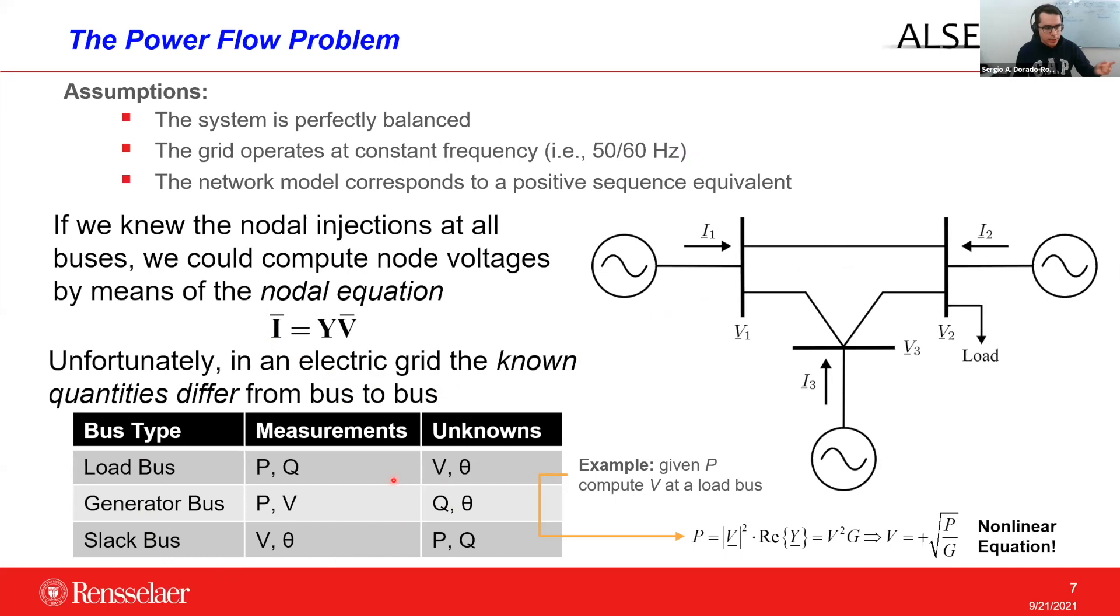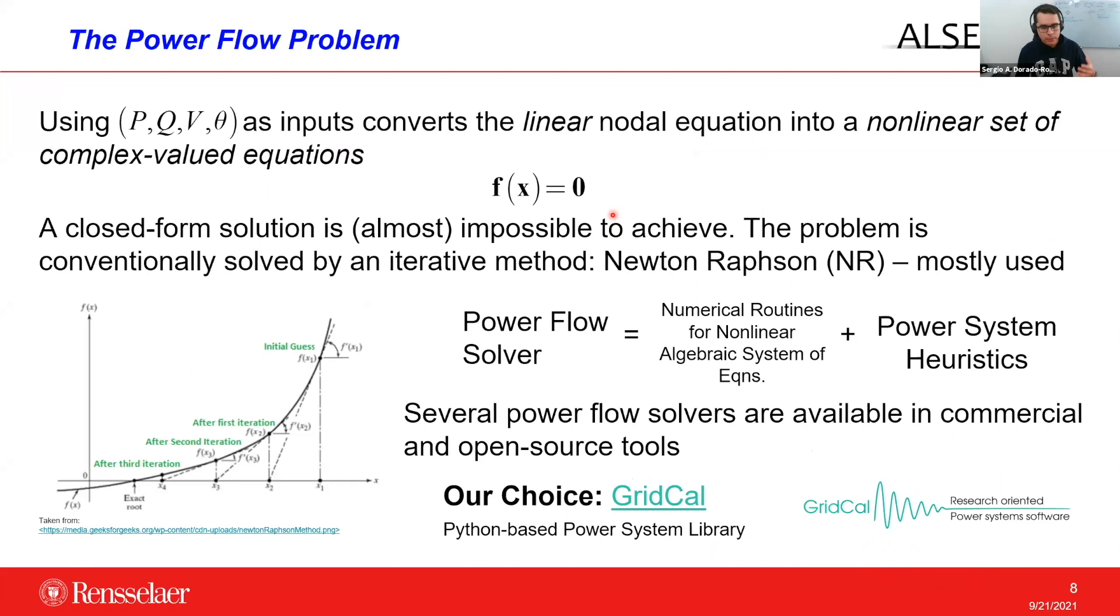For example, if in a load bus, we normally know the power consumption measured in active power and reactive power, but we don't know the voltage of that bus. If we, knowing P, try to compute V, the voltage magnitude, we would have to solve this equation here, and we would end up with a non-linear equation. So, basically, the power flow problem, from the mathematical point of view, it's a non-linear set of complex valued equations, and a closed-form solution for this problem here is almost impossible to achieve.